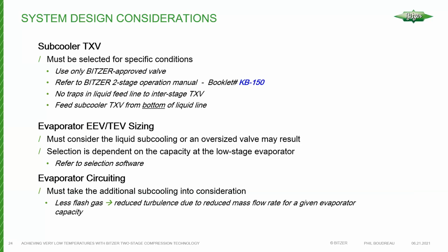Some system design considerations, subcooler expansion valve. Now this is something generally you don't have to worry about because the subcooler expansion valve would be provided with the compressor. In the case of a new installation, you have the expansion valve, you have the filter dryer, and the sight glass and the solenoid valve are provided as part of the Interstage kit. And we just need to know about the application so that we can provide the right orifice. Because obviously if you have an orifice that's too large, then you're going to have a hard time controlling the superheat of that valve. So it's application specific, it's refrigerant specific, it's compressor size specific also.